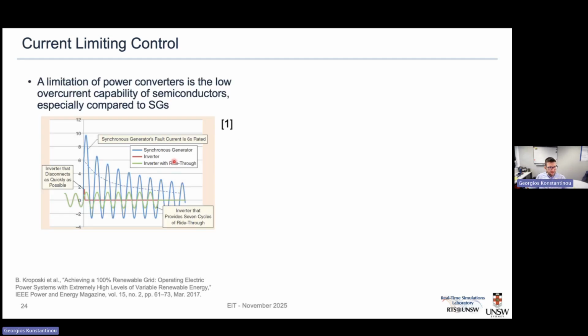So as an example here from this excellent report on connecting more renewables into the grid, you can see the differences with a synchronous generator. You have a fault, and the synchronous generator behaves with its transient and subtransient reactance that tends to be quite small. That gives us a very high value for the fault current, and this fault current defines the transient response of this generator. In a current limited inverter, if we do have this ride-through capability, we are still able to generate current, but this current is nowhere near the amount of current we would be getting from a synchronous generator, which creates all these additional issues and problems for the interface and for a power system which has more and more power electronics connected to it.